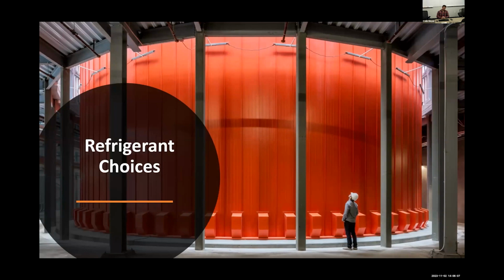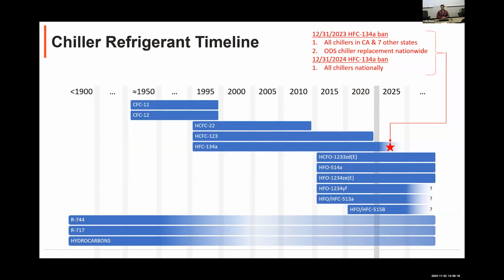A little bit about refrigerant, because that's closely related to these technologies and has changed a lot recently. So just an update on that. This is a simplified timeline of refrigerants that are available in chillers and heat pumps. And we've recently reached the end of the phase out of the ozone depleting substances per the Montreal Protocol. HCFC 123 was one of the latest refrigerants to reach its phase out date. So new chillers stopped being delivered with 123 in 2020.